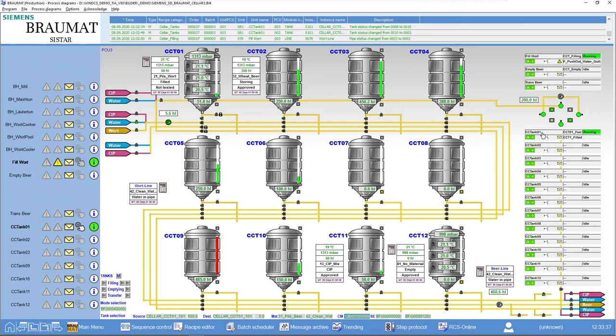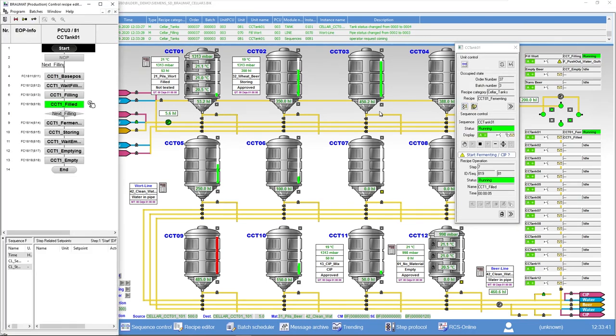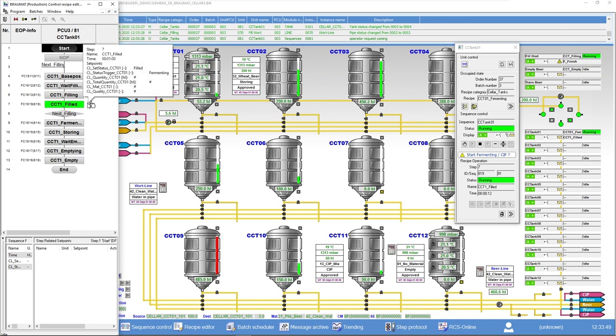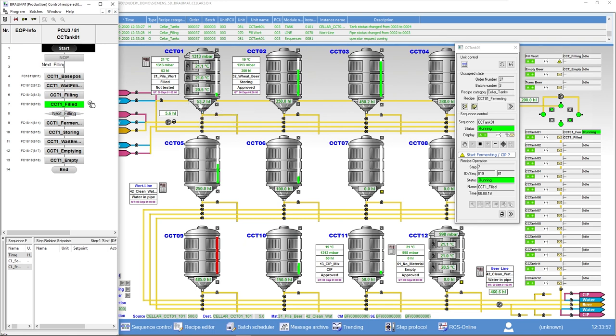Meanwhile, perhaps you have also noticed that we also have a tank recipe that was started automatically in a loop. This means that as soon as the transfer starts, the tank one subsystem also starts to run. The filling procedure has now taken place. We have transferred these 50 hectoliters, or in this case a little more. Now this tank is waiting on more commands.